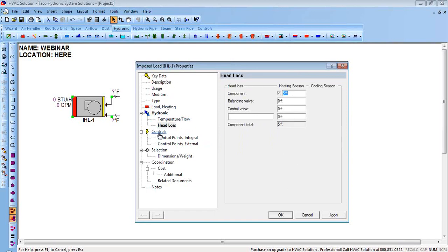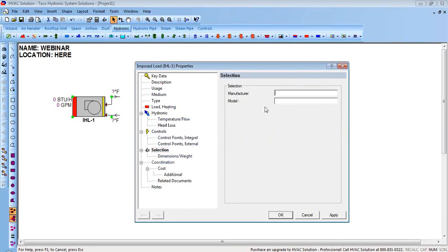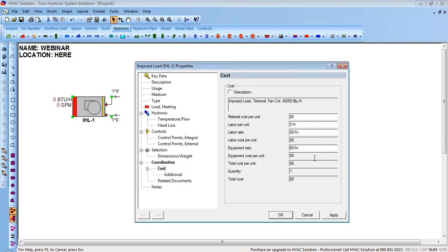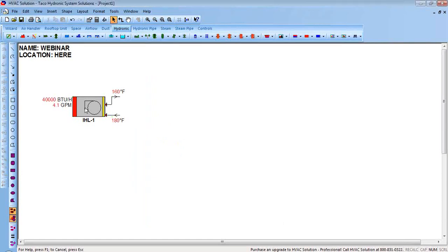If I have a specific manufacturer, I can type that in, and if I know the model, I can put that in too. I can also add dimensions and costs — the software can actually do a labor estimate if you wish. After hitting OK, it tells me I've got a 40,000 BTU unit with 180-degree supply and 160-degree return, so based on those conditions I need 4.1 GPM to get the 40,000 BTUs to this fan coil.